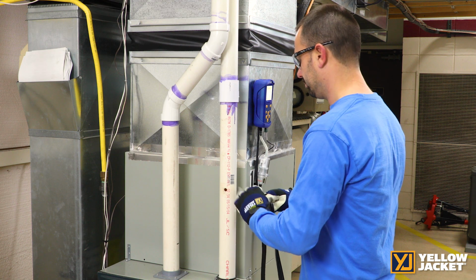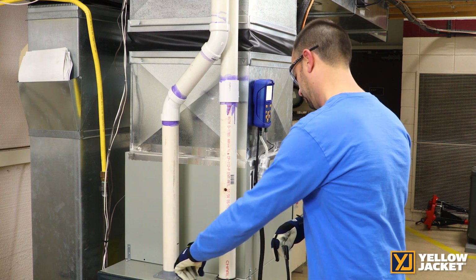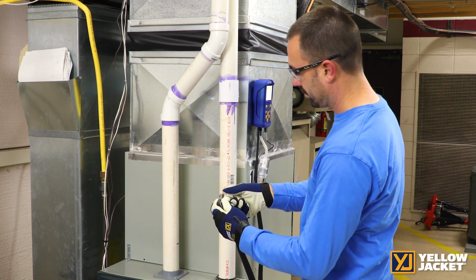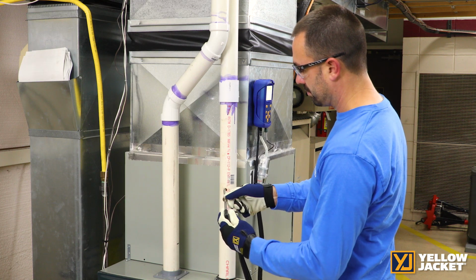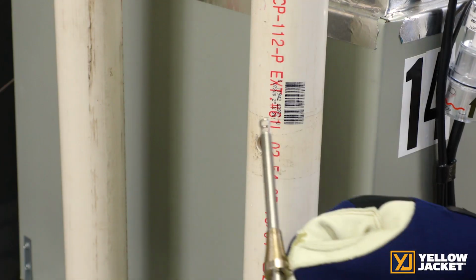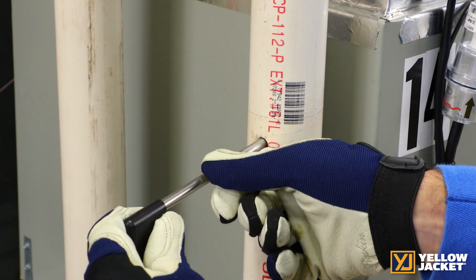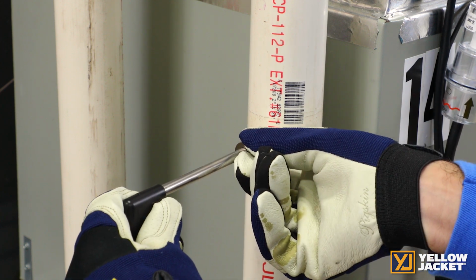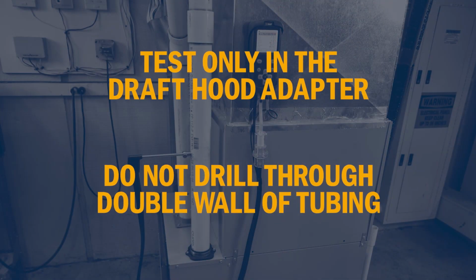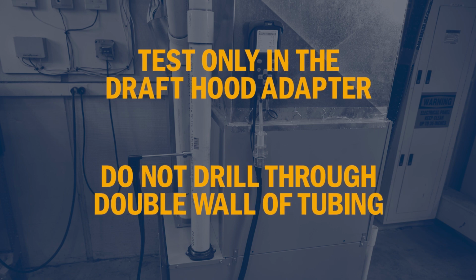Connect the analyzer to the exhaust flue to measure the flue readings. The flue cone allows you the ability to adjust the probe and keep it located while you collect your readings. It can go right in your high-efficiency furnace PVC tubing on B-vent systems. The probe should only be tested in the draft hood adapter, as you never want to drill through the double wall of the tubing.